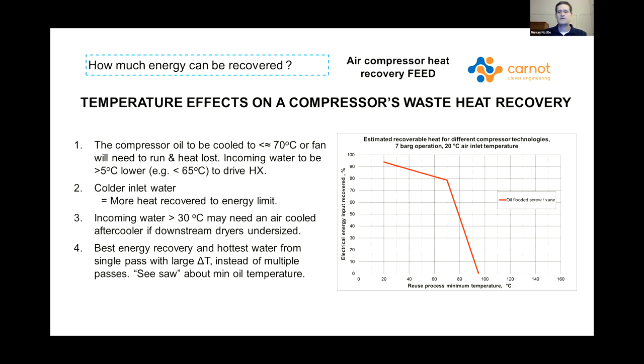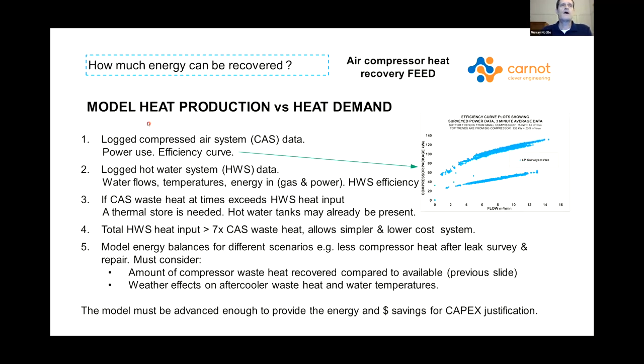So what do we actually need to put into an air compressor? There's lots of different bits and pieces you can do. So how much energy can be recovered? You've got to log what your compressed air system's doing. You know how much power is going into the compressor, and that will give you an efficiency curve like you can see here. You've got to log your hot water system, so you know what your water flows are, your temperatures are, what your energy is in terms of gas and power. And also this will pick up the mismatch between when your heat's being generated and when you're using it, and if you're going to need hot water tanks. If your hot water system demand is much bigger than compressed air heat output, you can go with a simpler design for a heat recovery system. So you need to be aware of all of that when you're trying to design your system.